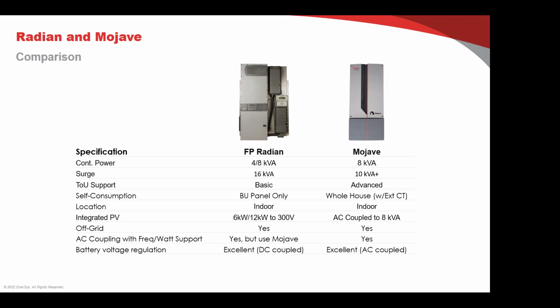And that's new. The other thing we can do that the Radian and what I've seen from other inverters can't: when there's very little power demand in an off-grid situation, AC coupled, and the batteries are full, it comes back to an unregulated charge, and we have to try and curtail that grid-dependent inverter. With Mojave, we'll do the same thing, but to protect the batteries, we just open up that pathway. So the batteries are always going to be protected.